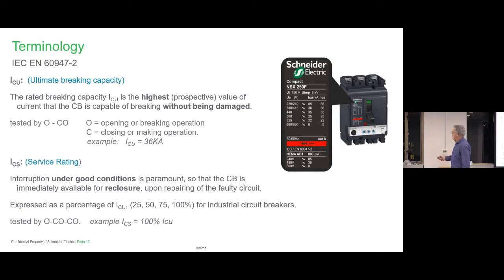But what do you know about this? Is that what the fault was when it happened there? Did it happen a lot further away and the fault was a lot less? The other answer I'm going to give you is that there are smarts now on breakers, on trip units, sorry. The trip units will give you contact wear. On large breakers, we give contact wear. And so we can see multiple faults on thermal, because we're only talking about, as you saw before, 130 to 150%. But on short circuits, we're doing multiple times. We're doing 10 times, 5 times. So it's major. As for the current that's going through there, the answer is I don't know, because every situation is completely different. But what you do know is that it is safe and it's been tested through that scenario. And guess what? If it has seen that, it will be knackered really, and it needs to go, and you need to replace it.